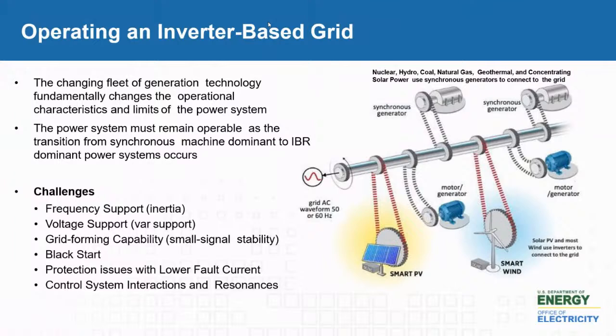Most of the protection systems identify the problem primarily by overcurrent conditions. When you have a fault, your impedance is significantly reduced and your fault current goes high, so you can see this high current, open the circuit breaker and isolate the fault. With inverter-based resources, your fault current is significantly lower, so you might not always be able to see overcurrent conditions when you have a fault. So it becomes tricky. What we're doing is developing different ways to protect the system based on signatures. We have high fidelity sensors that can recognize the signature of the fault, detect it, and then isolate it to prevent damage and threat to human life.